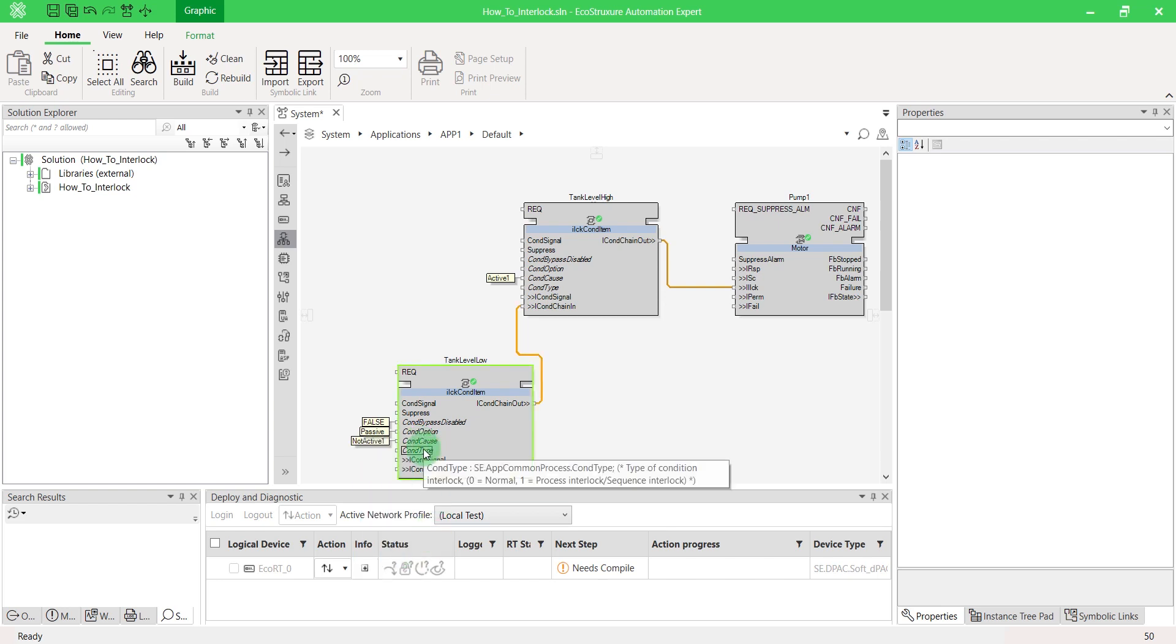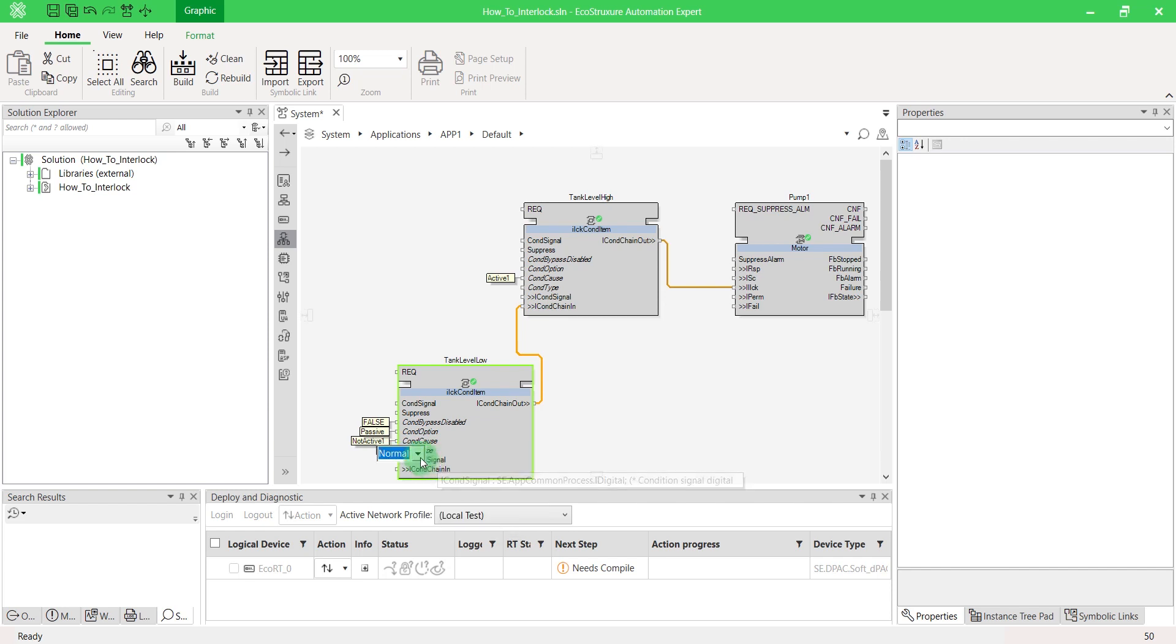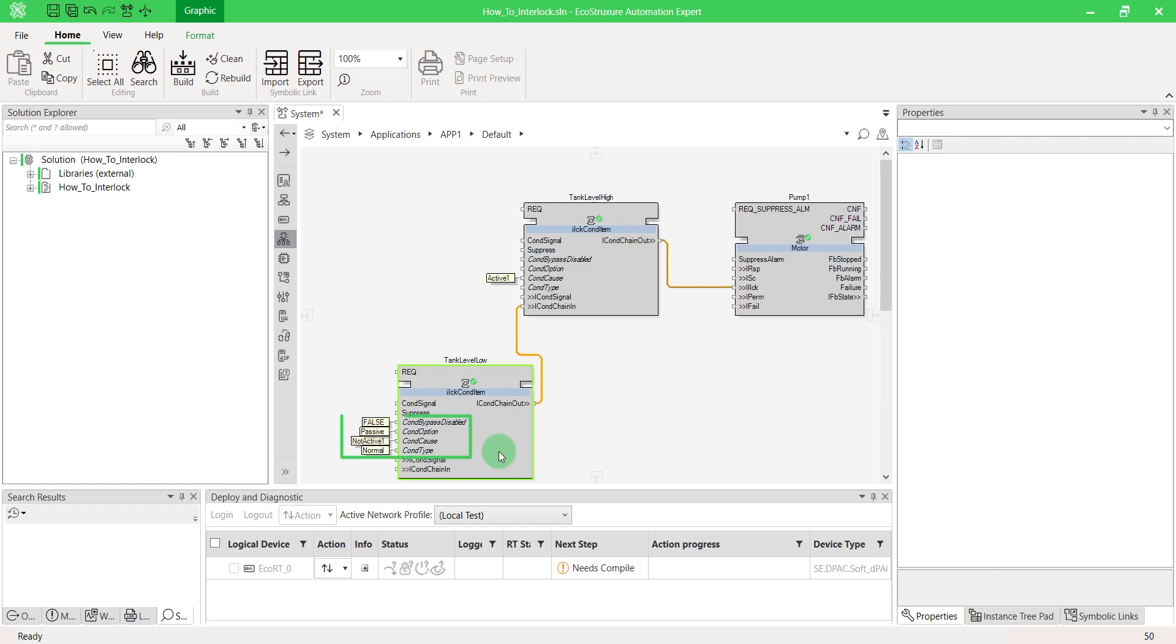Cond type is the parameter used to define the type of interlock condition. If the interlock is a sequential interlock of cascaded objects, such as starting interlock, then cond type can be set to process. Be careful. You cannot force those variables when a device is running. You have to change them directly in your project and redeploy the application.